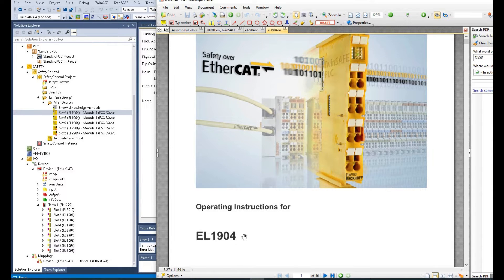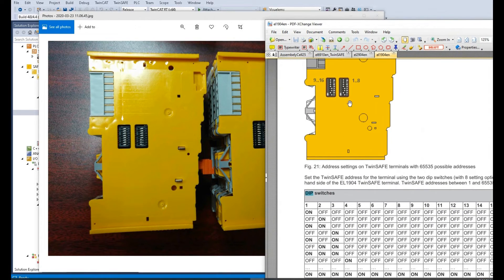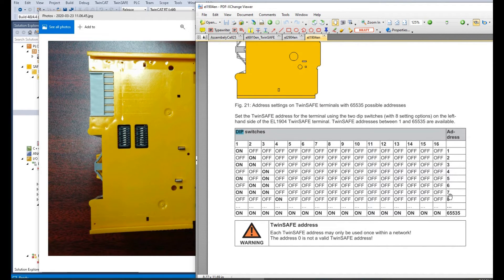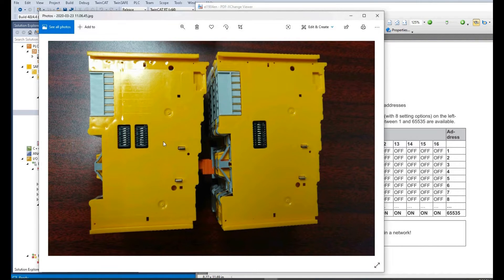If you want to check the detail, you can go to the safety manual — for example for the EL1904 safety input — and search for the DIP switch section. You can find this group is the low byte and this is the high byte. If you want to set the safety address to 7, numbers 1, 2, and 3 need to be set to ON. If you need to set the address to 8, DIP switch number 4 needs to be set ON and others set OFF. Keep this in mind and take care — you should set the DIP switch before you mount the modules together.